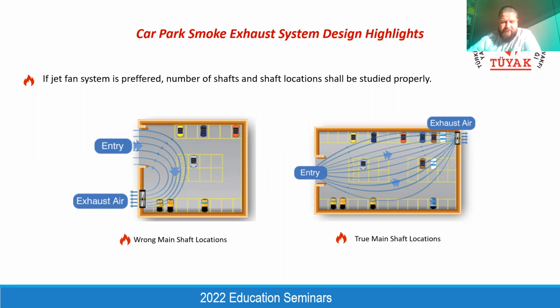And approximately for each 2,000 to 3,000 square meter of car park, you will have separate fresh air and smoke exhaust shafts, and these requirements will be given to you by the mechanical designer, but you need to have a minimum level of knowledge to understand and evaluate the requirements of the mechanical engineer, because you have to optimize the number of shafts and the location of shafts. If you don't know anything, the mechanical designer will require from you a maximum number of shafts to stay on the safety side of the design. But if you know that, you can discuss with them and you can optimize the design as well.